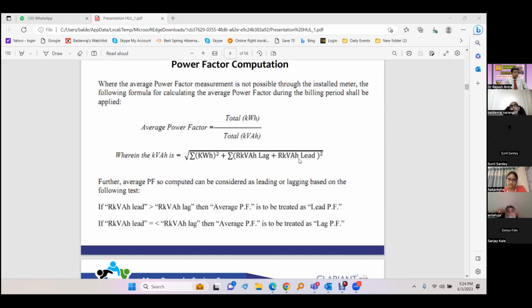We had some cases where people came to us saying that our bills have shot up like anything. After this provision was made, people who were getting a 7% incentive started getting maybe a 15% penalty. One company we found was getting a 35% penalty. Although they reduced the penalty to half after introducing this kVAH billing, it was still so high. And it was a result of using excessive power factor correction capacitors without any requirement.